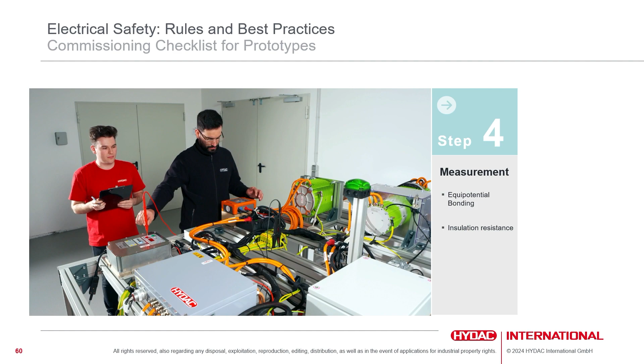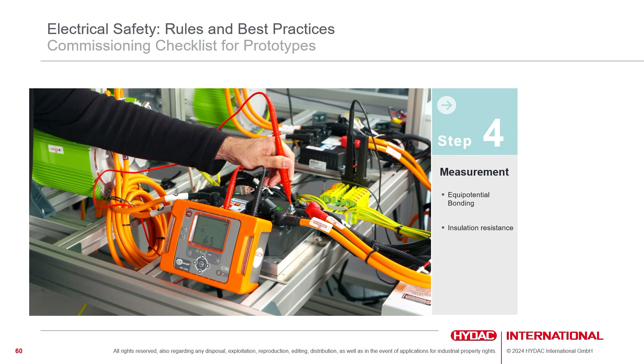The second important measurement is insulation resistance, where you check insulation from both DC plus and DC minus to chassis. If either is missing, the chassis could become connected to DC plus or DC minus, causing a hazard of electric shock, which is quite common. Those are the basic measurements you need to do.